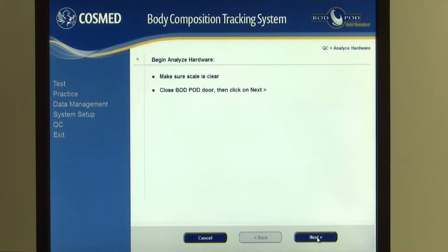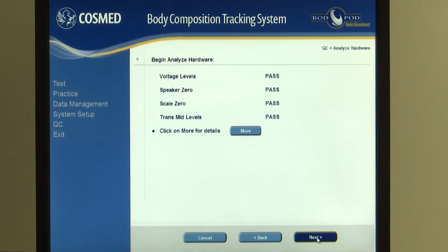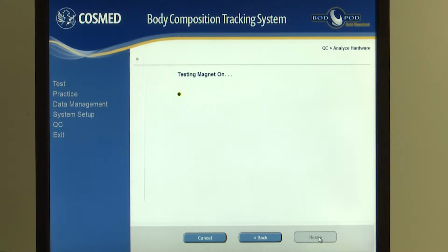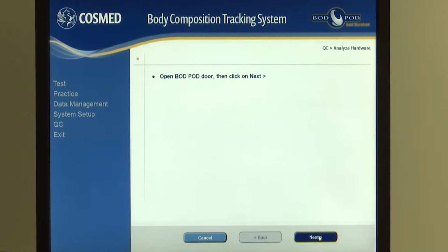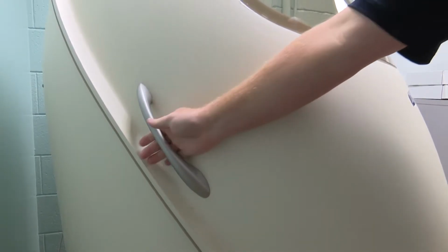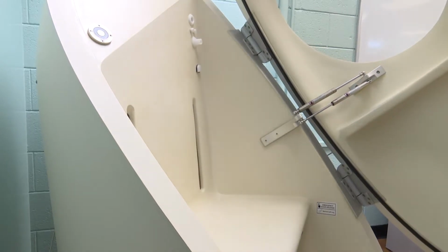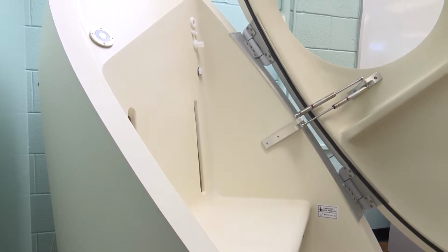This tab will not be able to be clicked unless it is dark blue. After each step, the software will state if the analyzation test was a pass or fail. If it fails, the test will need to be repeated. If it passes, click on Next and resume the analysis. The software resumes testing of the magnets and the airway valves. The next portion of the calibration process is to determine the amount of air that is currently in the Bod Pod itself. This process takes approximately 45 seconds.